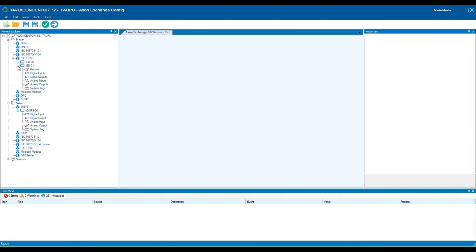Axon Exchange is a communication gateway and in this case we will use it to convert the data sent by the simulator bay through MMS to the DNP3 protocol.